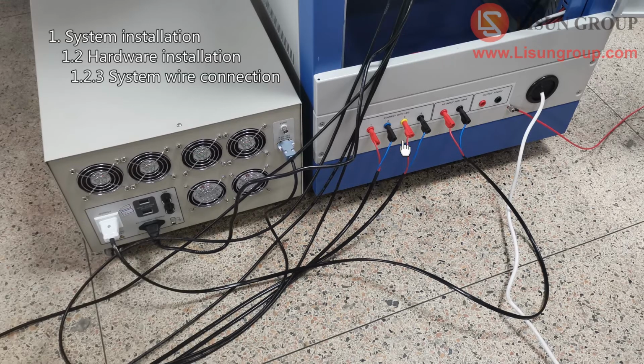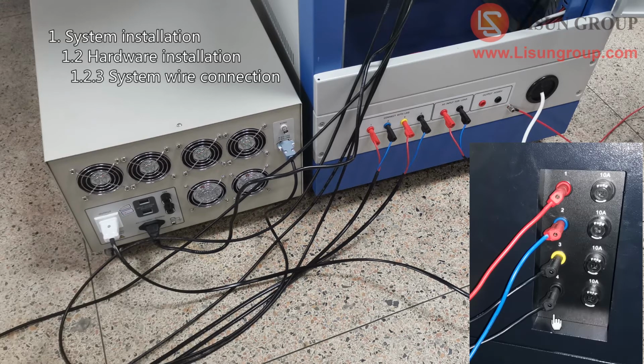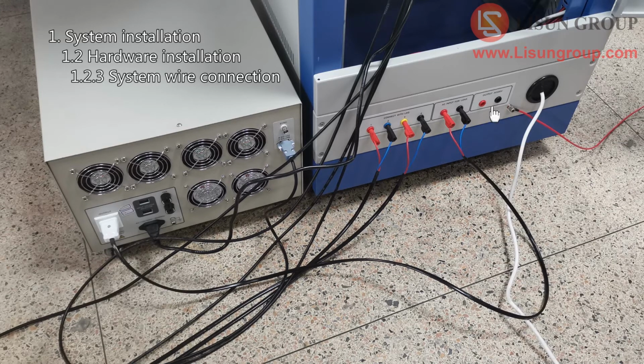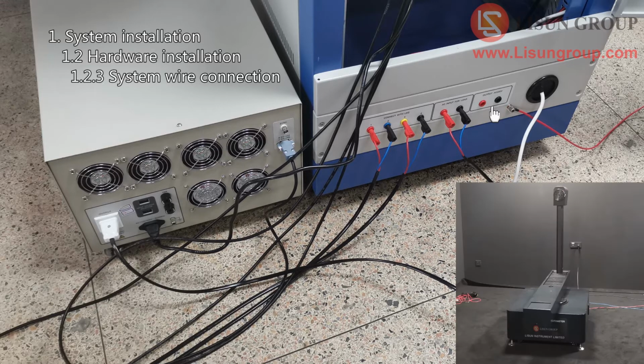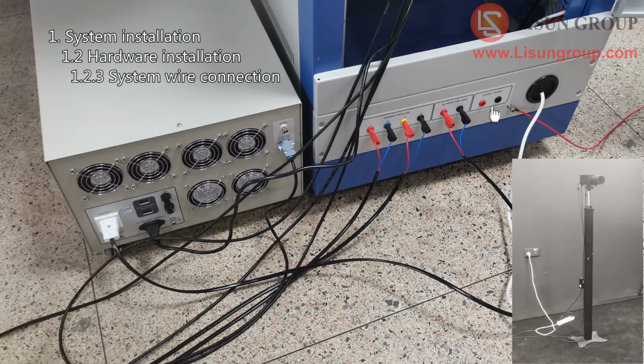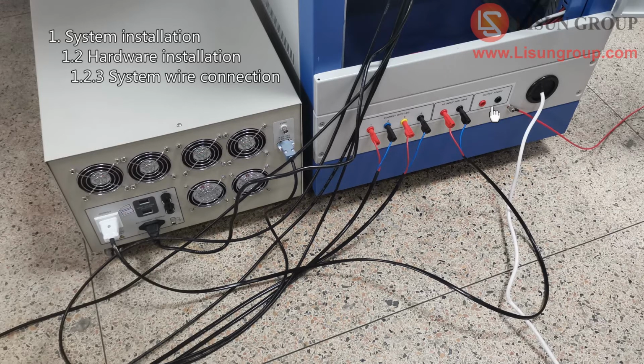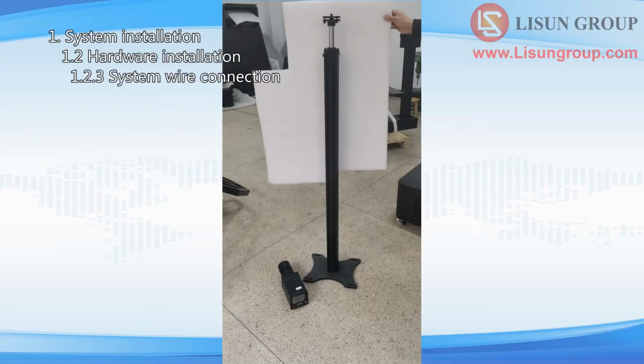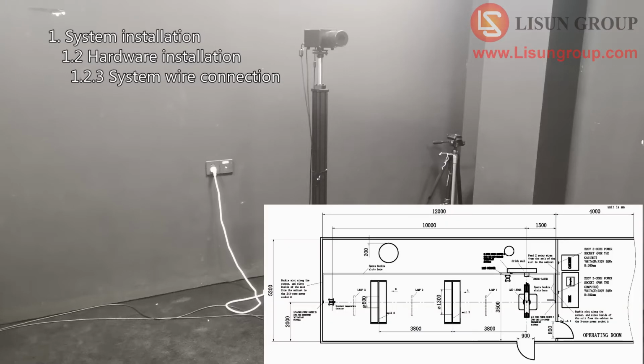There are 4 terminals marked with numbers on the back of the cabinet. They are used to connect with the goniophotometer. These two terminals are connected to the power strip inside of the cabinet. It is used to power darkroom equipment, including the goniophotometer, photodetector, spectroradiometer. Then you can control the power supply of the entire system on the cabinet. Connect the grounding terminal to the ground. This is the photodetector and its holder. Assemble it and put it to the correct position according to the darkroom drawing.